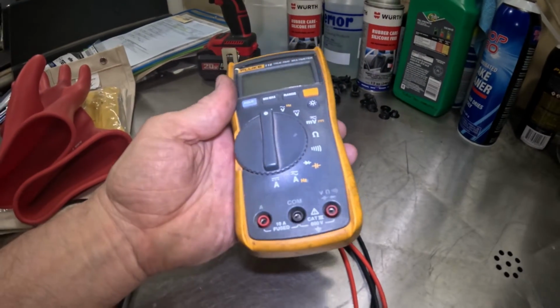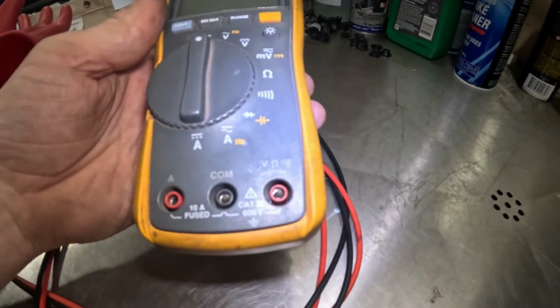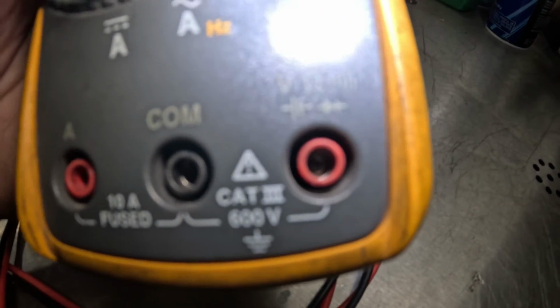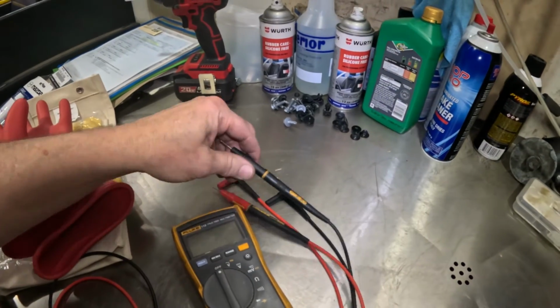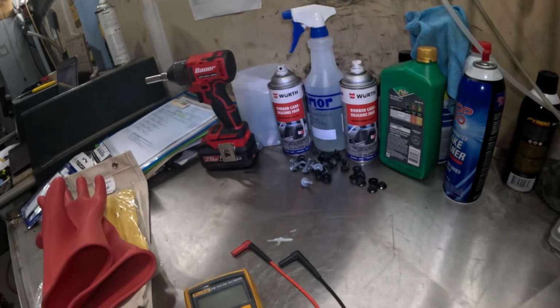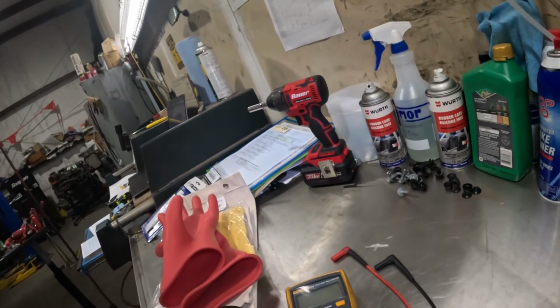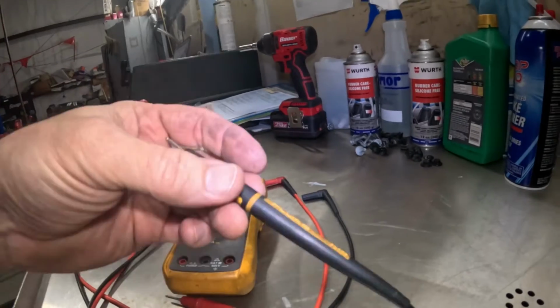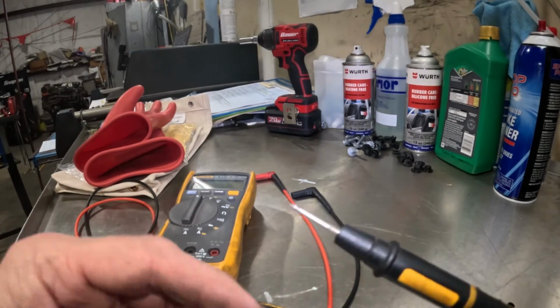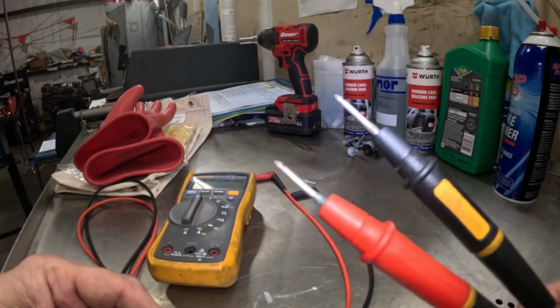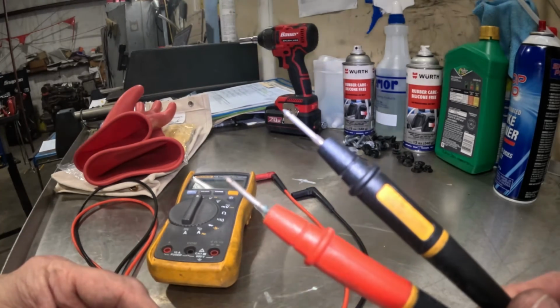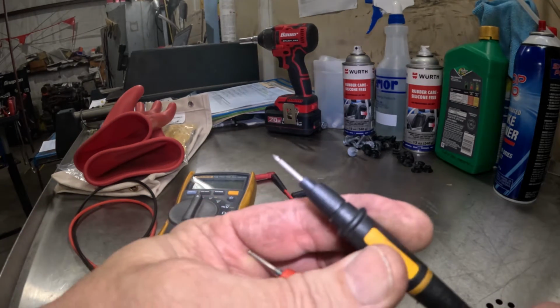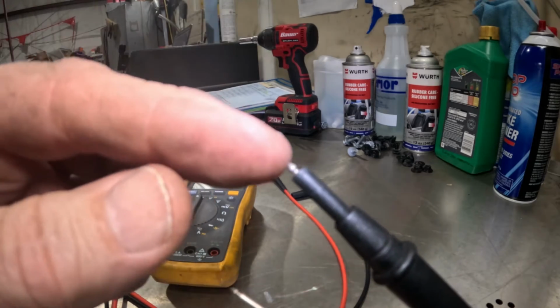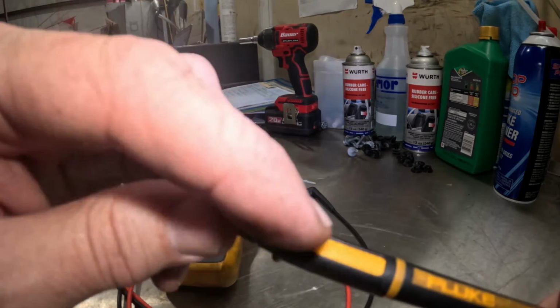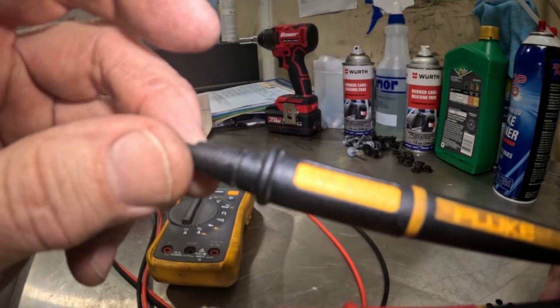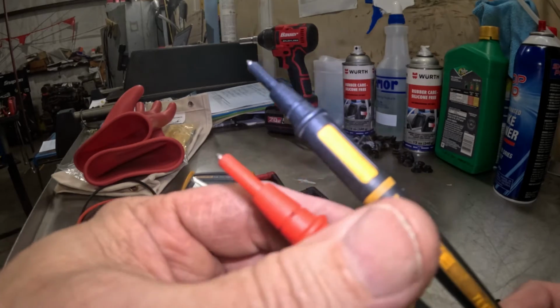You need to make sure your meter is Cat 3 rated - you can see this is Cat 3 rated, 600 volts. It's the same with these leads - they have to be rated to Cat 3 also, otherwise you could blow them up, you could blow up your meter. These are special leads because high voltage can jump from terminal to terminal. They have a special sleeve that moves up on them, so only the tip is shown, and when that tip is shown, this shows that it is Cat 3, rated up to 600 volts.